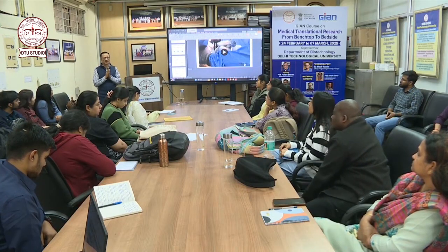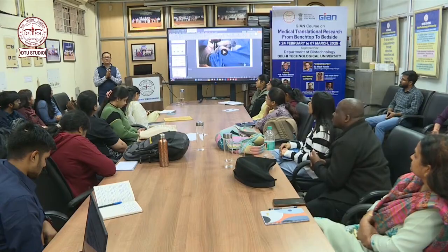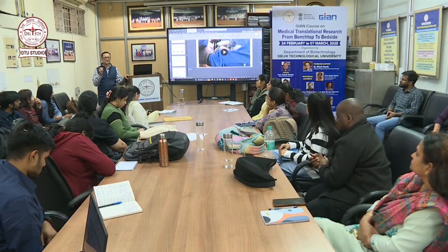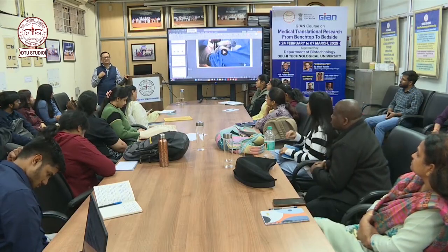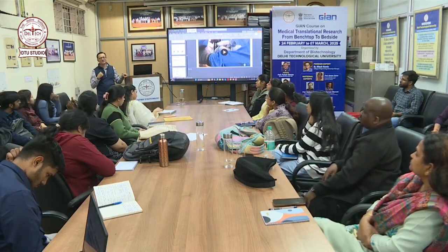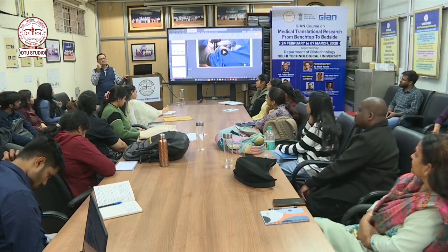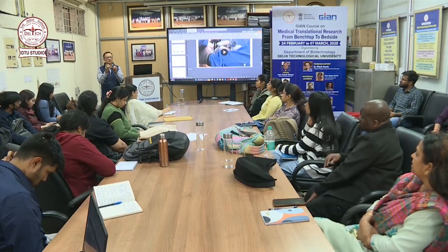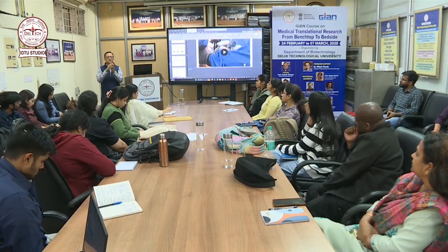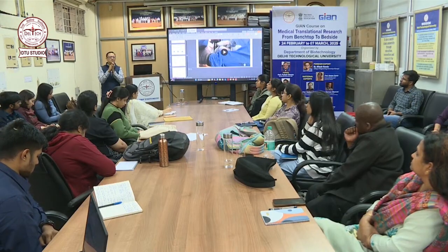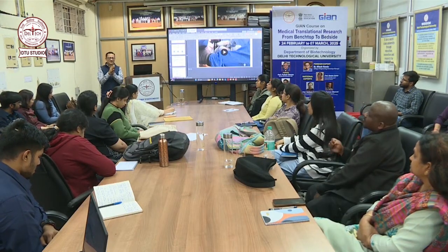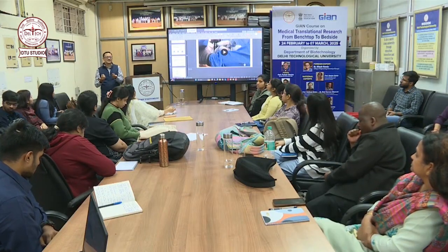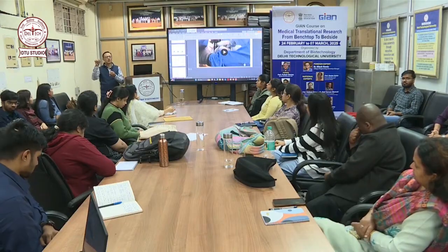That's the purpose of my tubing. But when you have a vascular graft, now that can be a little bit porous material, because when you put a vascular graft, and we will talk about vascular grafts later, there you want the cells to grow, and these pores can be used for cells to grow, because there you are not using it just as a tubing, you want it to become more part of the body. But when we are using catheters, that porous material might increase complications for us, and we don't want those pores.